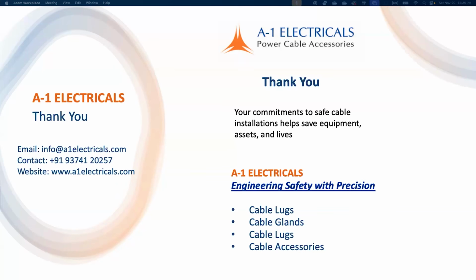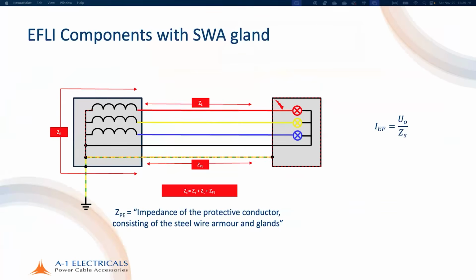Mr. Ravi Teja Baru asks, how viable is it to rely on armor for earth fault protection? Does IEEE 80, IS 732, IS 30... If yes, no, sir, it is absolutely valid. If you make a proper connection, it is a great way to achieve automatic disconnection of supply. You say dedicated. This is dedicated. It is a dedicated connection. As per the product standard, the armor has a certain resistance, and it is made to withstand a certain amount of fault current. If you use the correct type of gland, you can absolutely rely on the armor to be a protective conductor. It is a dedicated protective conductor, and there is no inductive loop that is formed.